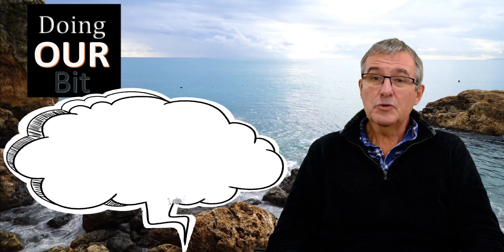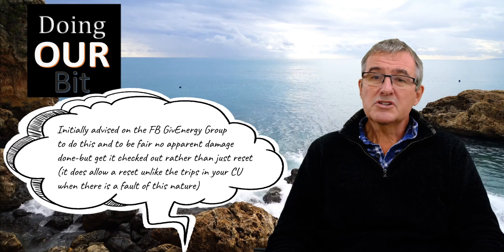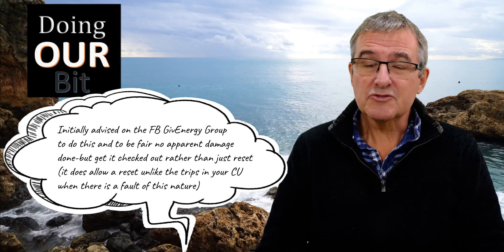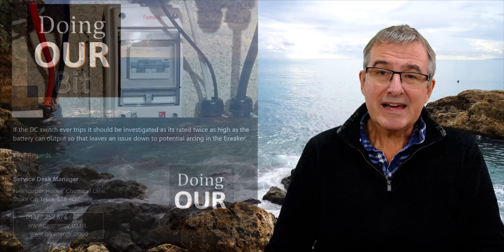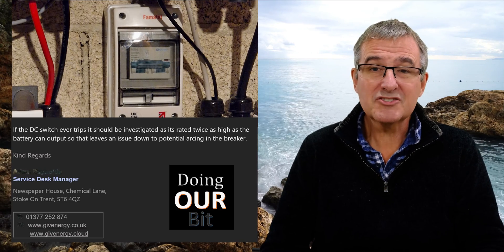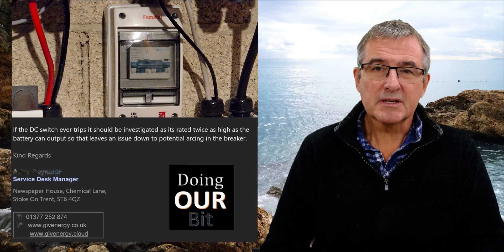You can just reset this, and I did this on a few occasions, and then it started happening quite frequently. I really wish I'd known what I now know, which is the reason for this video — that trip is designed to take twice the actual load that it should do, so when it does trip it definitely shows there is a problem with the system that needs to be investigated by your installer.